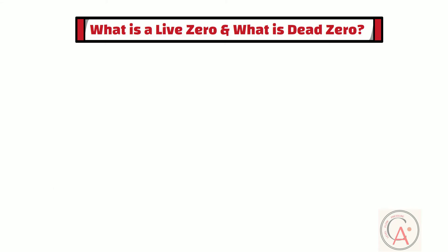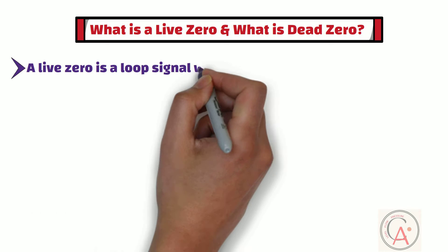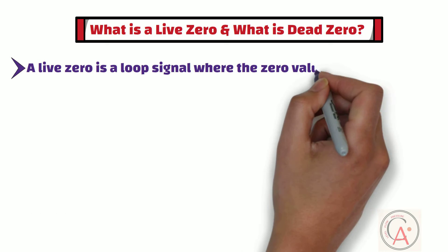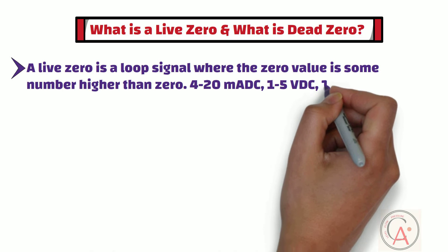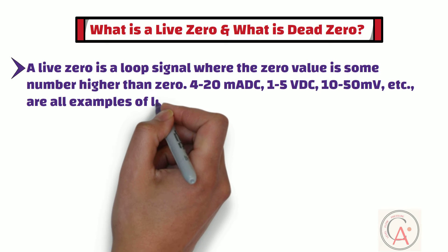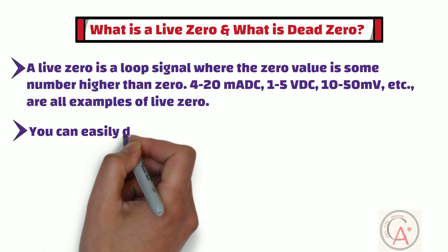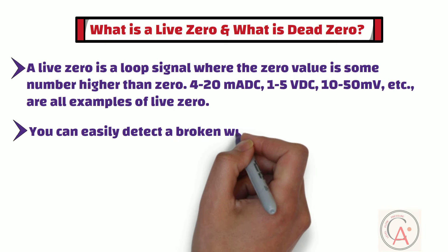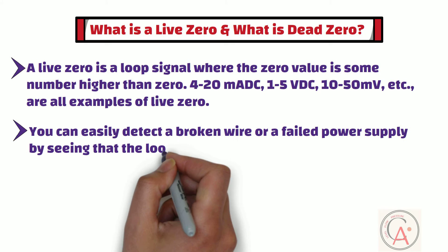A live zero is a loop signal where the zero value is some number higher than zero. 4-20mA DC, 1-5V DC, and 10-50mV DC are all examples of live zero. The significant advantage of a live zero is that you can easily detect a broken wire or a failed power supply by seeing that the loop reading is zero.